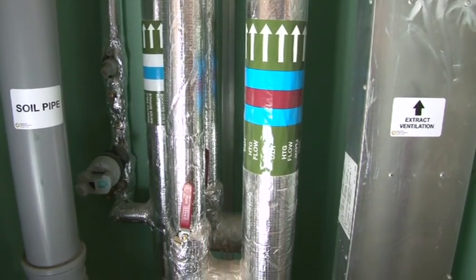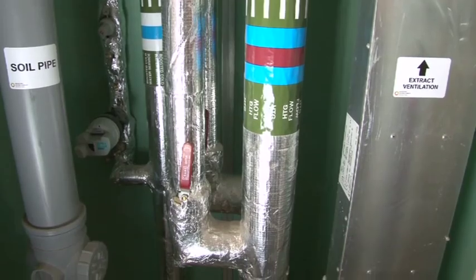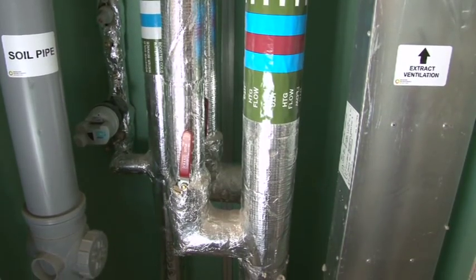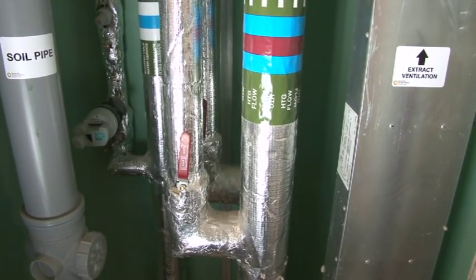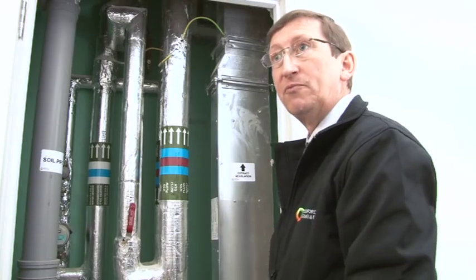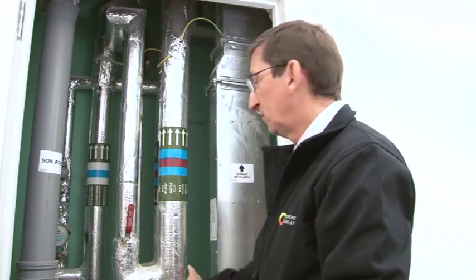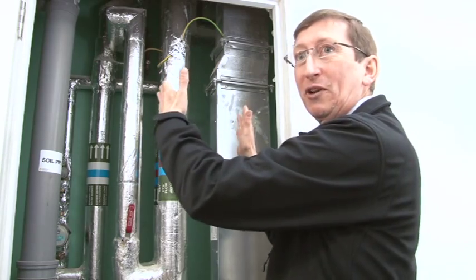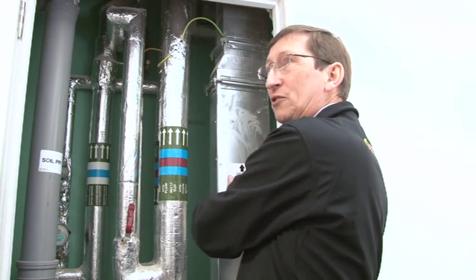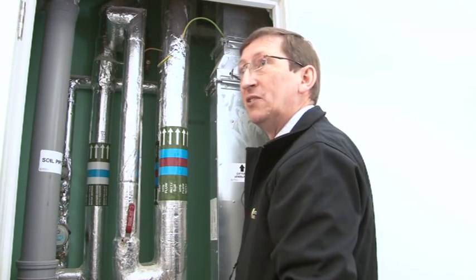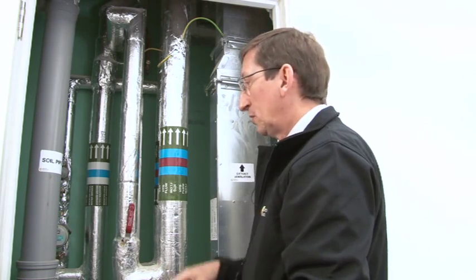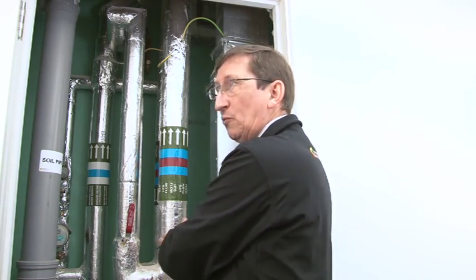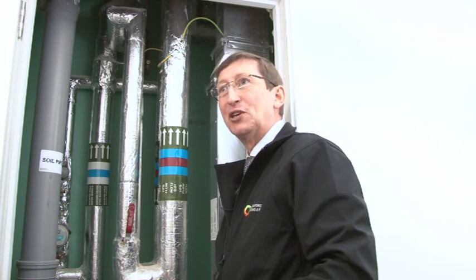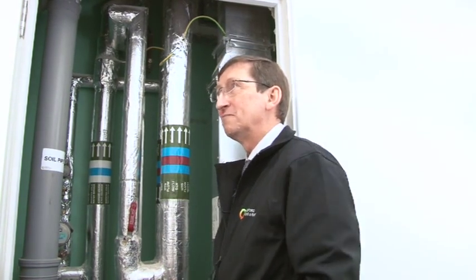So this riser, with the flow and return from the heating, is feeding all the flats at this point in the building. It goes vertically upwards and then feeds the flats on all the different floors. If there's a problem in this riser, all the flats in that column will have an issue, as they would with the ventilation if there was a problem with that side of it. But if the water flow in this one fails, it won't affect the flats on that side of the corridor. They'll still get their heating.